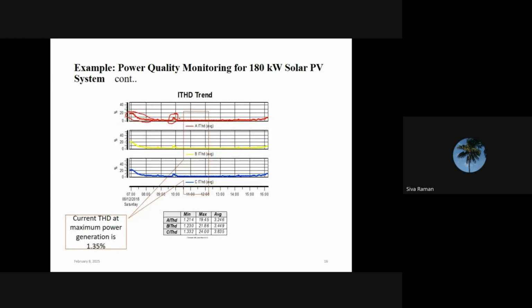Sometime back I told you why the TDD method is used instead of THD. The reason is that during lesser operating conditions, it will calculate more THD. You can see that when the plant is delivering a very small amount of power, the THD value is a little bit high. If you take this value for compliance, then absolutely it is a higher value. This is the nature of power electronic converters. In order to avoid this kind of situation, the TDD method was introduced later. During the peak generation time, the maximum THD is 1.35 percent.